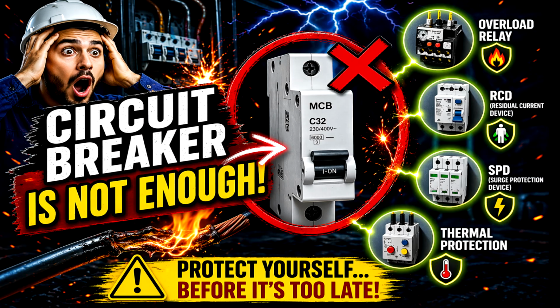Yes, you heard that right. Let me explain it simply. A circuit breaker is designed to protect you from only two things: short circuit, very high current, and overcurrent. But there are much more dangerous problems that the breaker might not even notice. First danger, slow overheating. What does that mean? A wire carrying a load slightly higher than its capacity. Not enough to trip the breaker, but enough to slowly heat it up over time.